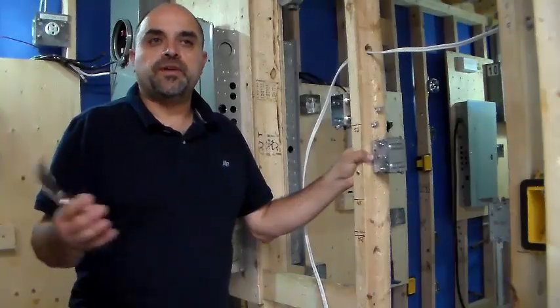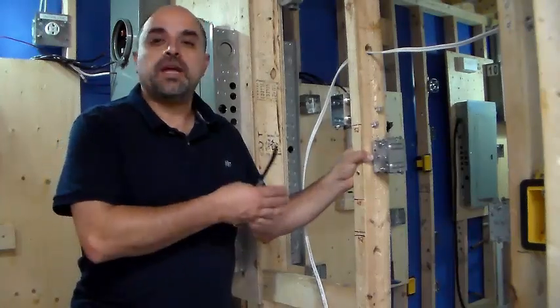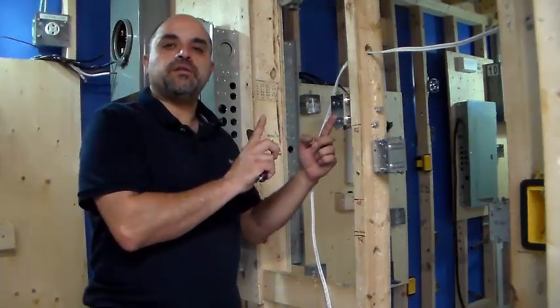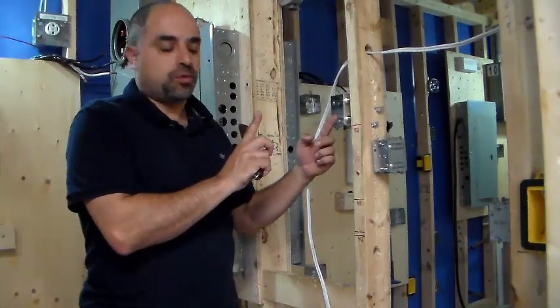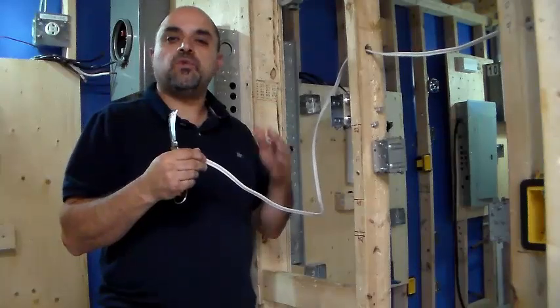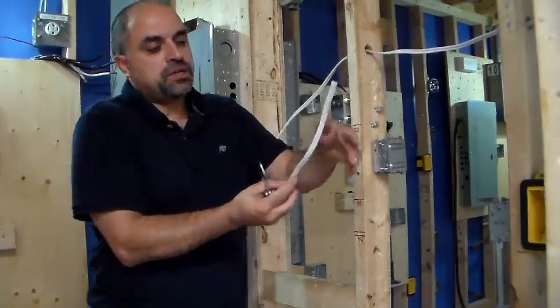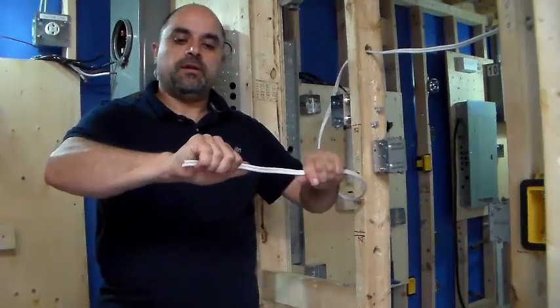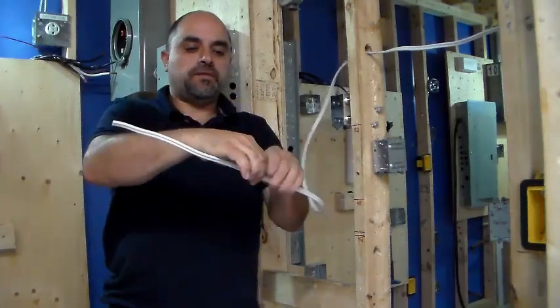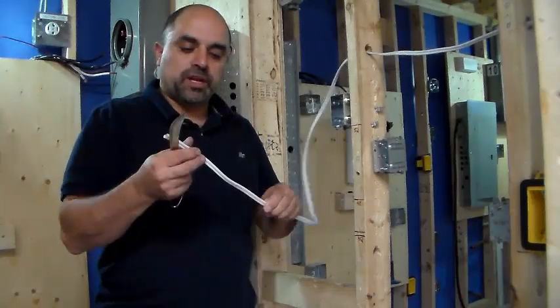Now that we know some of the materials and devices and boxes and connectors and staples that we're going to be using, we can now move on to the proper way of installing the cables into the boxes. In general, most boxes require to have at least six inches of wires after they've been installed in the box. That is due to Canadian code. So how much of this wire outside sheath do I need to strip so that when I'm done I have six inches of wire? I usually use the ten inch rule and I can usually line it up between here and my elbow, roughly ten inches. Or you can take your hand with the thumb out and the fist and that should be about ten inches. The more experience you have, you'll learn to quickly decide what is ten inches.